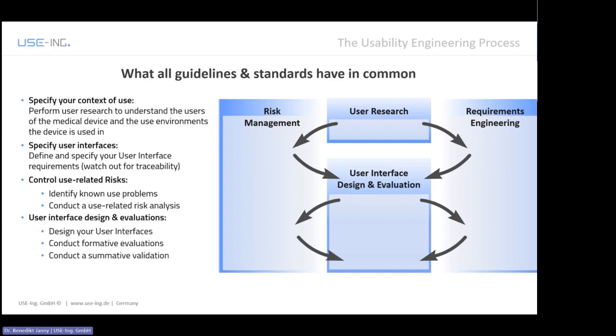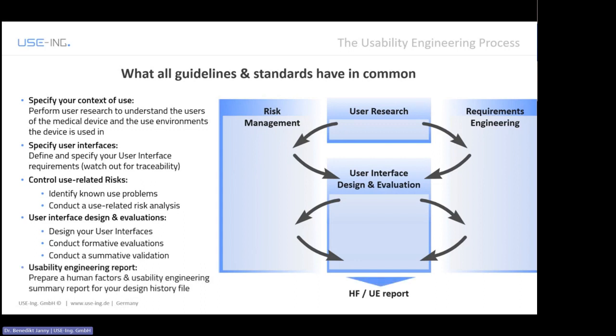Of course, we then must design our user interfaces and perform formative evaluations accompanying product development. Finally, we must conduct summative validation or human factors validation, as it's called in various parts of the world, mostly done in the form of a usability test, and prepare a summary describing all usability related activities for our design history file.